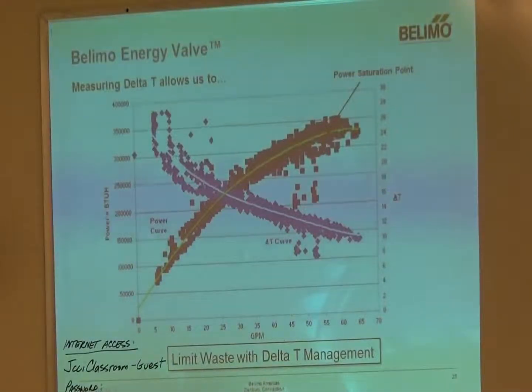So here we're looking at measuring the delta T, and the way we can do that is because we have the temperature sensors built in there. You can see here we've got our coil output, so that's the power of our coil, and we've got our delta T coming down here. Up at the top, the power saturation point, which on this graph I think they marked a little early, is really when that curve flattens out, because that's when you're not getting any more heat transfer out of your coil. When that happens, that's where you should set your delta T.